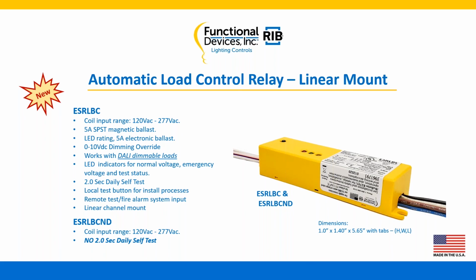Now, what we did from that, we created a second model, and it's primarily when you think about it from the controller standpoint. If you're using a wall switch for the LBC model, you're seeing that 2-second delay. But when you're using it from a controlled environment, it changes things, and that 2-second delay needs to be scheduled through the controller. So what we've done with this ND model is created a no 2-second delay daily test, or no delay in shutting it off when you do. Again, that was primarily focused on controllers needing to schedule their testing and report that to their inspectors.